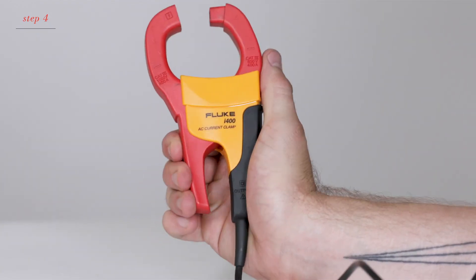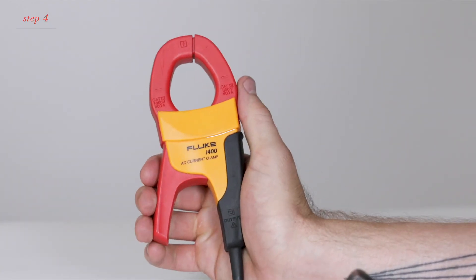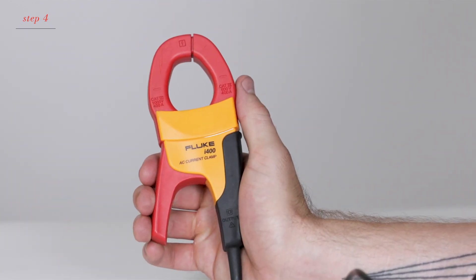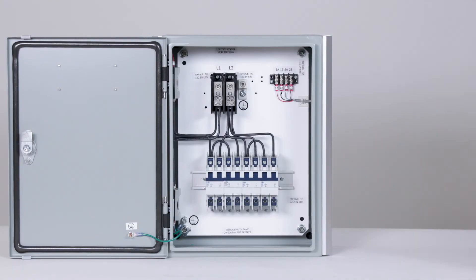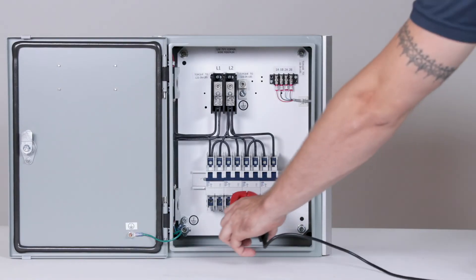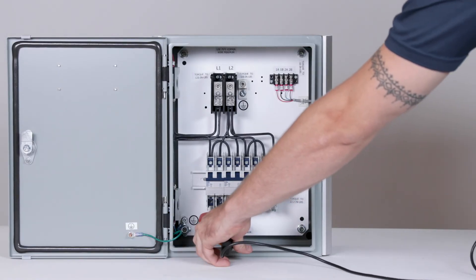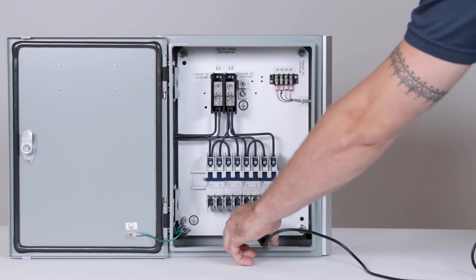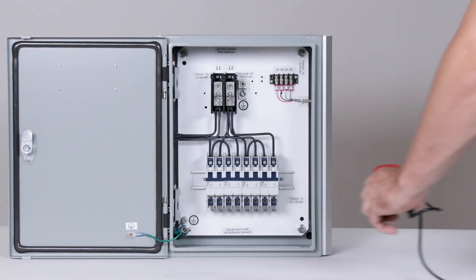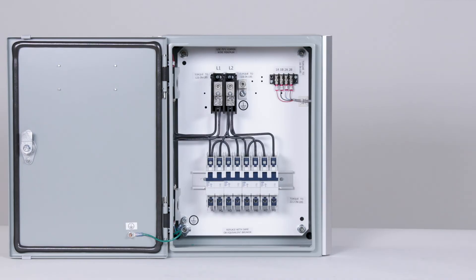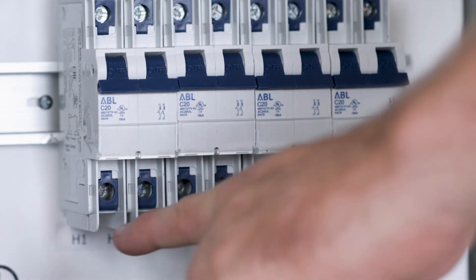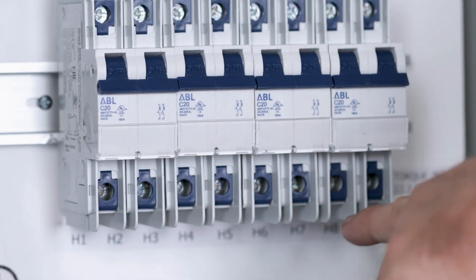Verify if the heater is pulling the specified amperage. You'll need to take the reading using an amp clamp at the output of the breaker associated with the heater. You can find this at the bottom of the panel.